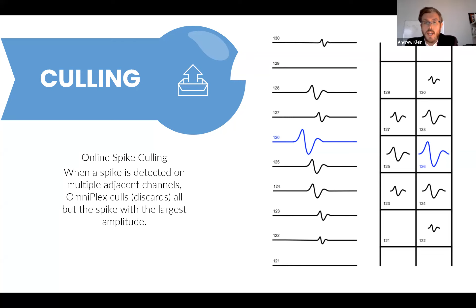Next, we will talk about changes to the way users can select which types of data and which channels are saved into a PL2 data file. In the new version of OmniPlex software, wideband recording is enabled by default for all channels to facilitate use with third-party array sorters offline, which typically perform high-pass filtering to extract a continuous spike signal for waveform thresholding. Also, since field potentials from high-density probes are typically nearly identical between nearby sites, Plex Control defaults to record only one of every 8 field potential channels. So channels 1, 9, 17, etc., as shown in the chart on the right hand of the slide.